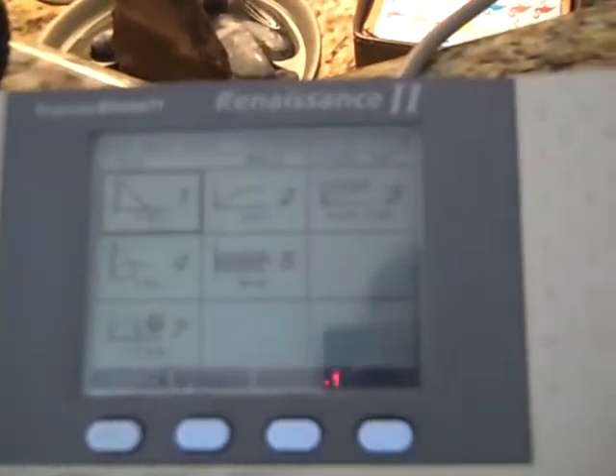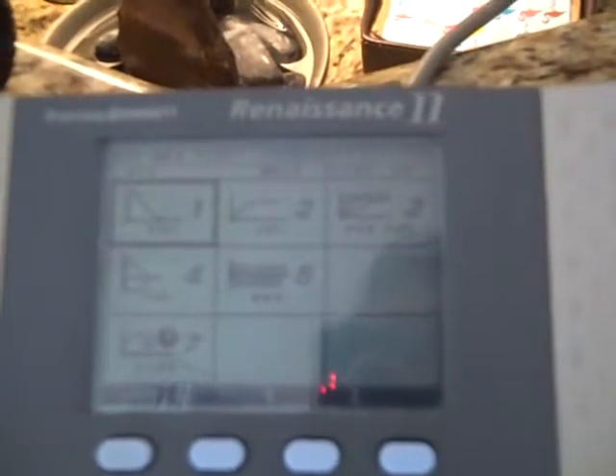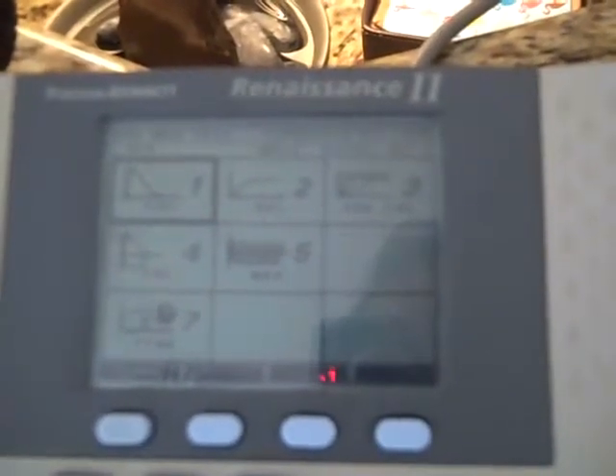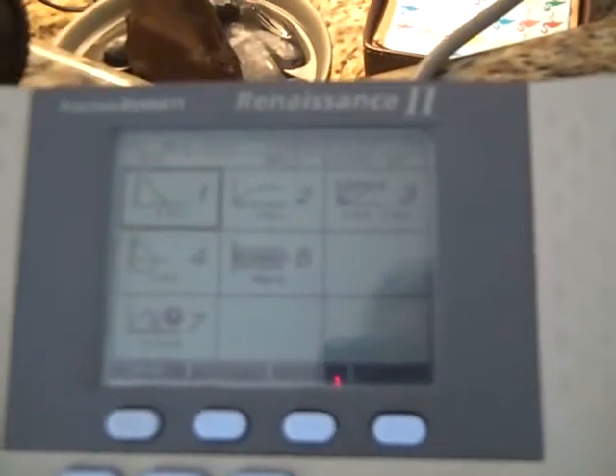And then this screen says number 1, new patient, 2, test, 3, view, 4, edit, and so forth. You hit number 2 here for test, and then the next screen that comes up will have number 1 be FVC, number 2 is SVC, number 3 is SSD Cal, and so forth. You want to hit number 1. You'll always hit number 1 on this test. So we always want to do an FVC, number 1.